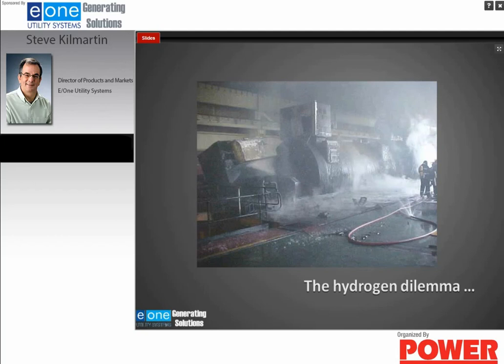This is what happens if you don't keep the hydrogen inside the generator. This generator happens to be located in South Africa. The problem here was that the seal on the exciter end, which is closest to us, leaked hydrogen into the exciter cab. The exciter cab has a collector ring in there, and that collector ring, if not aligned properly, can have some arcing and sparking that takes place. In this case, the hydrogen escaped into the exciter cab. There was some arcing there that caused the explosion, which then caused the fire in the generator.